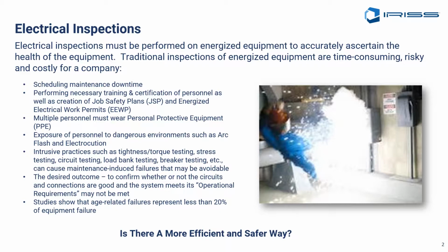The desired outcome, of course, is to confirm whether or not the equipment and the circuitry are in good operational, working condition. And sometimes, physical tests may not be the best way to actually ascertain that that's the case. So a lot of these technologies that are available can really help you do that. The other thing to keep in mind is that while we certainly have aging infrastructure in our facilities, age is not necessarily the primary driver of equipment failure. In fact, most equipment failures, almost over 80% of them, have nothing to do with how old the equipment is, but rather other factors that play into the equipment failing to provide its designed task over time.